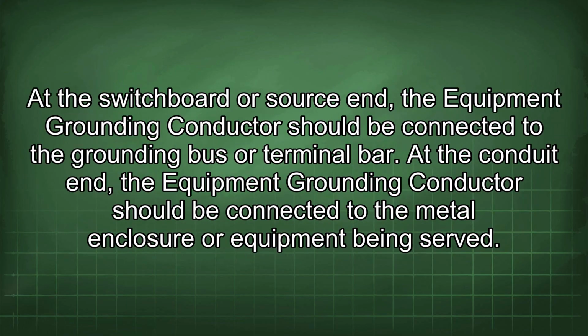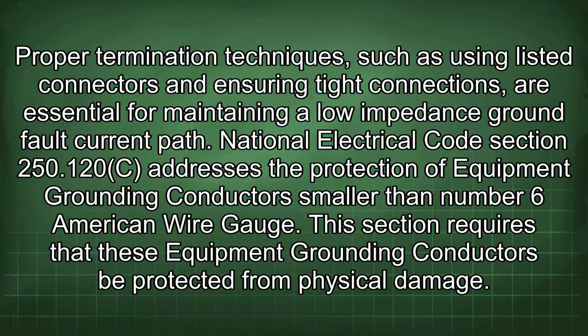It is crucial to terminate the equipment grounding conductor properly at both ends of the liquidtight flexible metal conduit run. At the switchboard or source end, the equipment grounding conductor should be connected to the grounding bus or terminal bar. At the conduit end, it should be connected to the metal enclosure or equipment being served. Proper termination techniques, such as using listed connectors and ensuring tight connections, are essential for maintaining a low impedance ground fault current path.